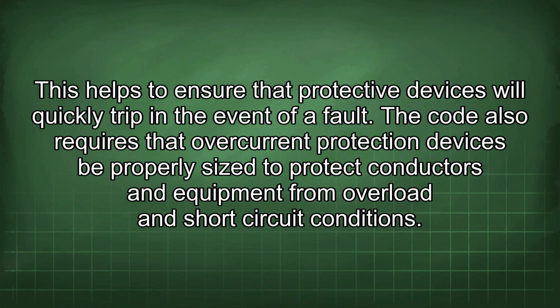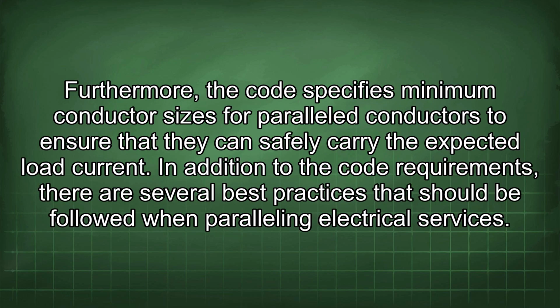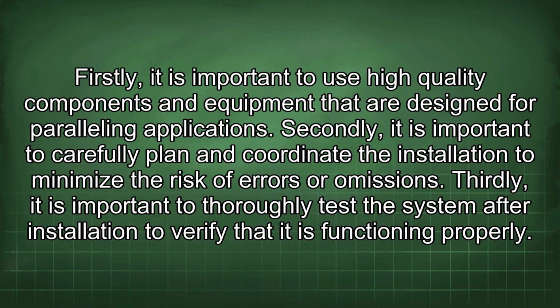The code also requires that overcurrent protection devices be properly sized to protect conductors and equipment from overload and short-circuit conditions. Furthermore, the code specifies minimum conductor sizes for paralleled conductors to ensure that they can safely carry the expected load current. In addition to the code requirements, there are several best practices that should be followed when paralleling electrical services. Firstly, it is important to use high-quality components and equipment that are designed for paralleling applications.